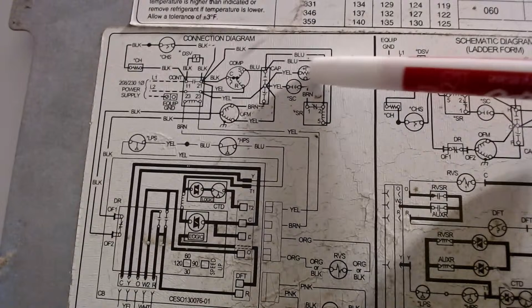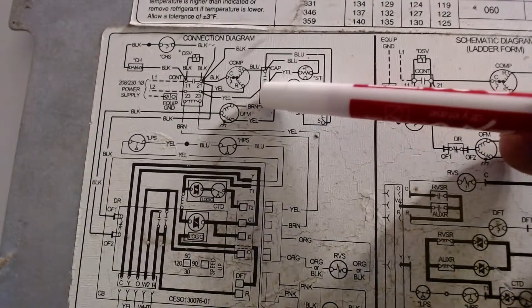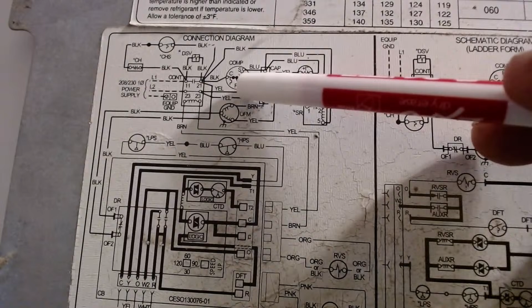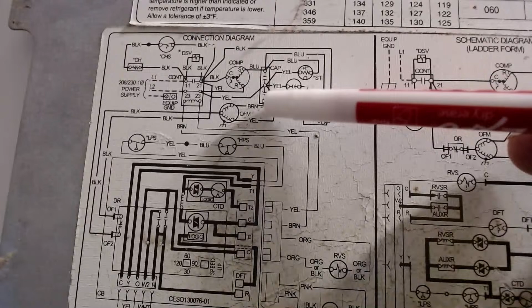The last terminal we have is our run. That comes off of 23. That's our 240, that's where we're making our connection. Yeah, the other wire coming off of 23 comes over into our capacitor. So this side is 120, and the common side is 120. So this is where 240 gets thrown through at it.